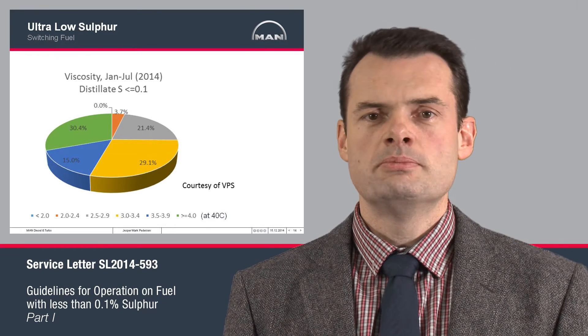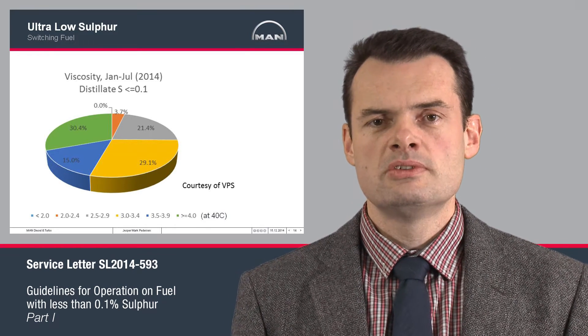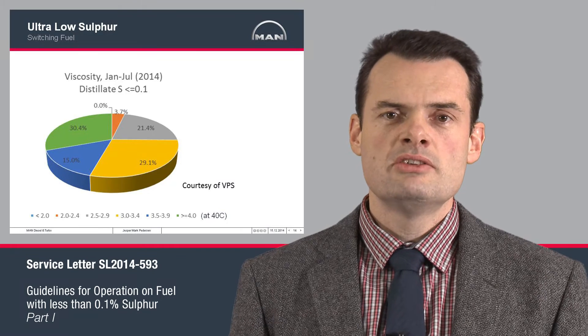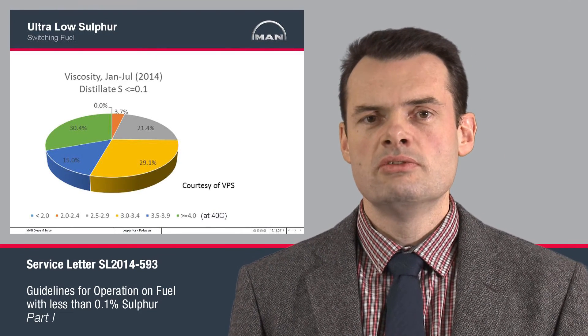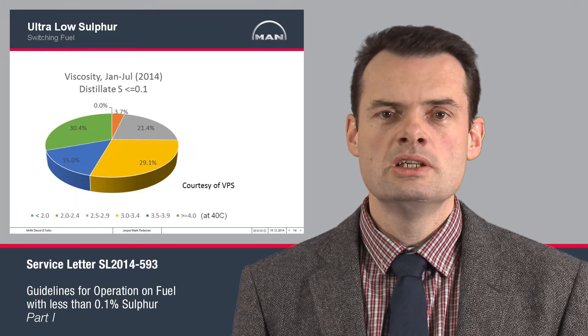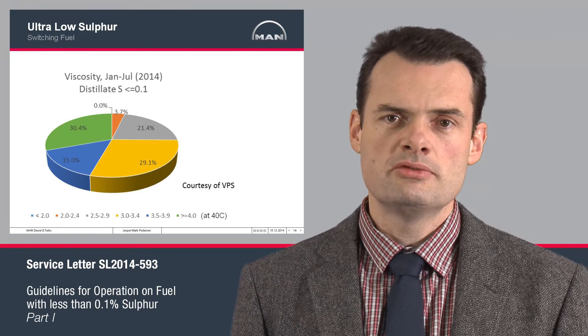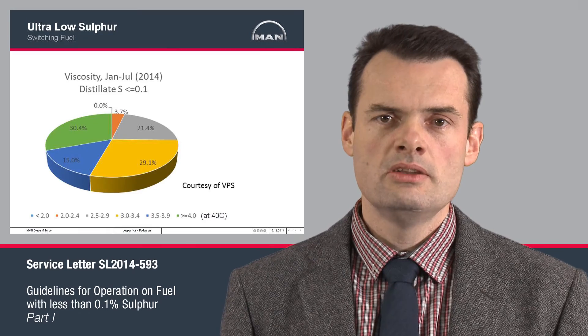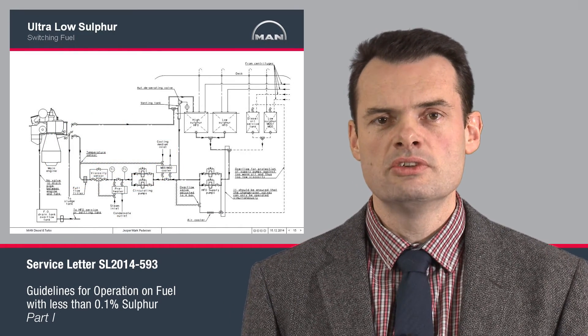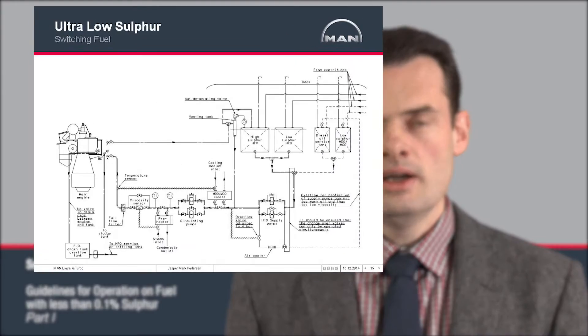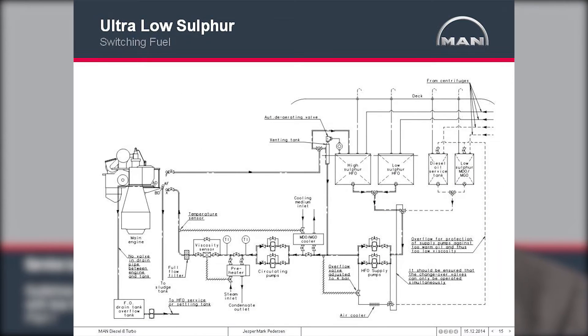Looking at distillates bunkered for ships, they come in different viscosity variations, but luckily the predominant part of bunkers received for ships are usually with viscosities higher than 2.5 centi-stoke. This makes it much easier to maintain an adequate viscosity on the main engine — higher than 2 centi-stoke, preferably 3 centi-stoke — and this can be done by using fuel coolers operated with central cooling water.